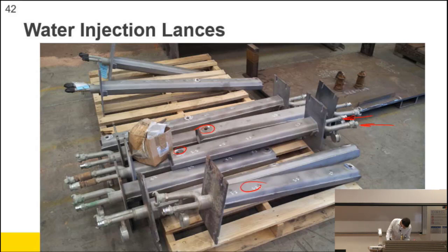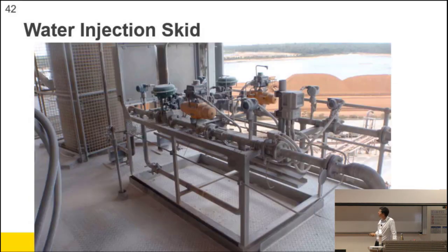We are doing thickness tests. Right, so you take an ultrasonic thickness tester, and we're just checking to see if the particles are wearing the lances. That's a very hard and high temperature rated steel. This is the air, compressed air and water. I forget which one's which. They're different colours at different points.